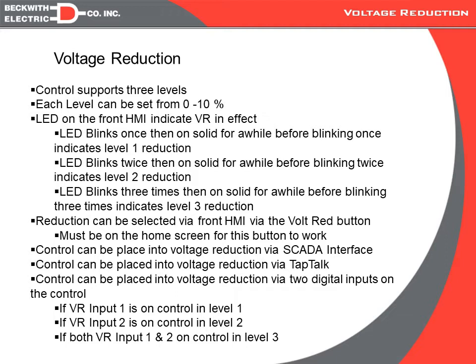Now, we can place the control in reduction from a front button on the control locally, or we can do it via our SCADA interface, via DNP3 commands, or via TapTalk, either locally or remotely, or a final way is via hardware, where we have two voltage reduction digital inputs available on the control, and between those two we can get 3 levels of reduction.